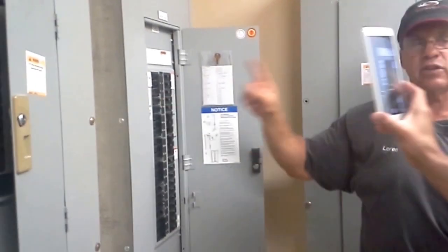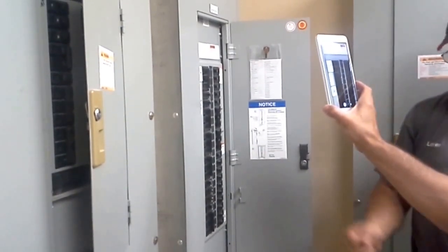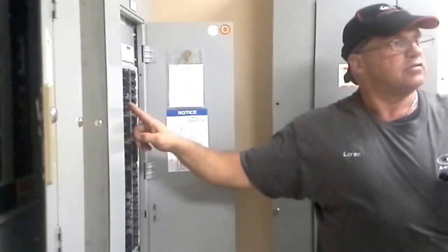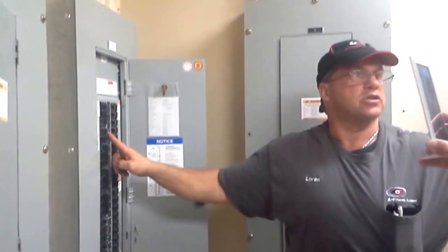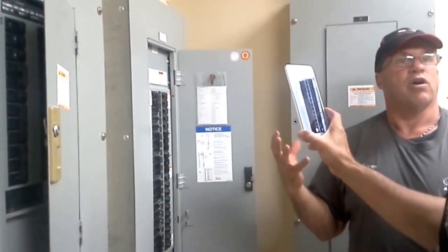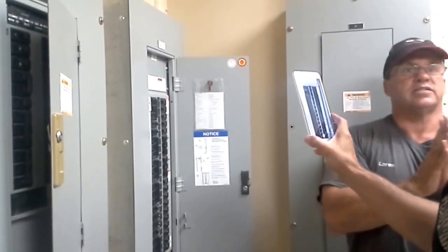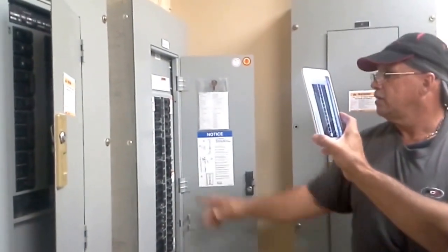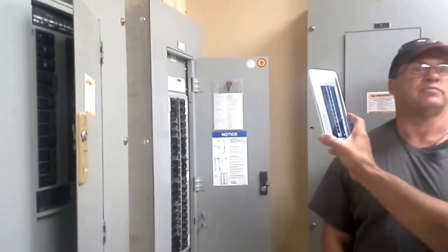Because when you connect the new battery, the charger is going to say, I need to charge you at full amp because I'm not getting anything until you touch that battery. When you touch the battery out there, you can blow that controller out. That H panel, you can blow that digital controller out, because that also lives on that 12 volts, and all of a sudden I'm getting a current spike. Once you're connected, then you come back over here and put your battery charger on.